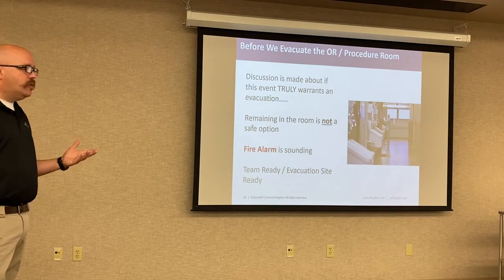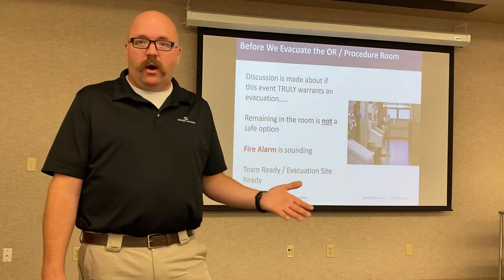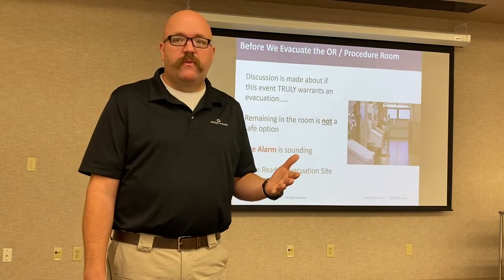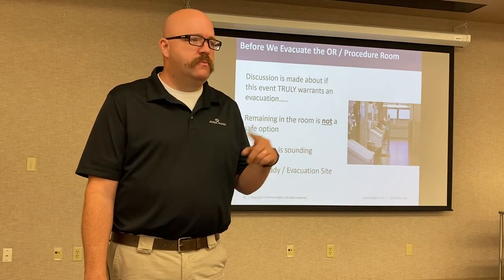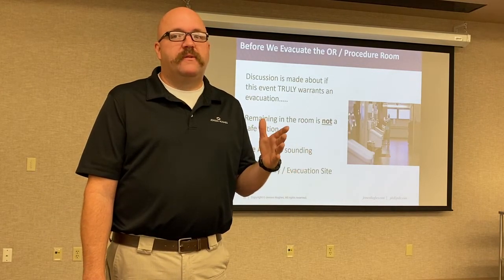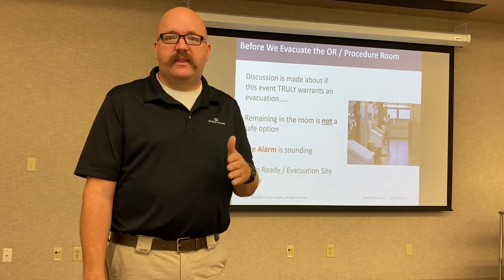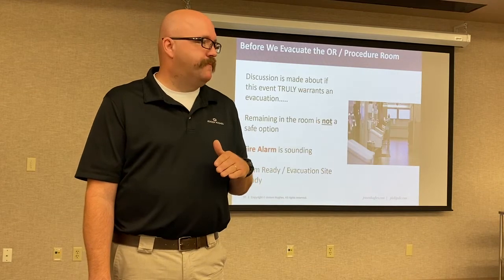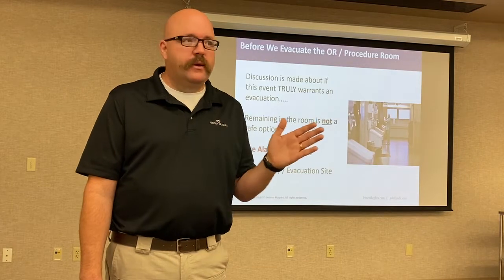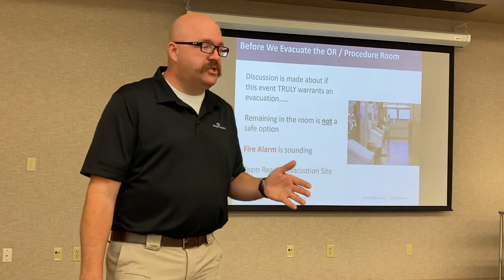Again, knowing what to do when there's a fire next door in an OR, right? Do we stay or do we go? And it's all based on, I haven't seen the ORs because I've never been here before. Do they share a substerile room in between? Okay, so if they share a substerile room, that means that if the neighboring OR is on fire, we have to do the same exact thing. If they're gonna evacuate, that means we go too, okay, if we're in that space. Because there's no firewall, there's no fire doors in between there. Yeah, there's a door, but that only provides us with very limited protection.